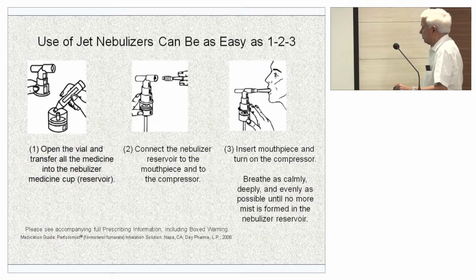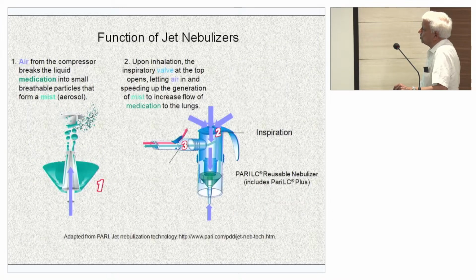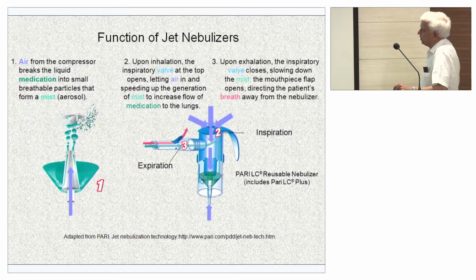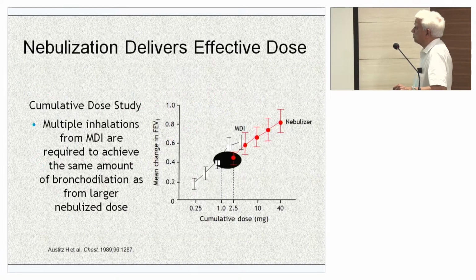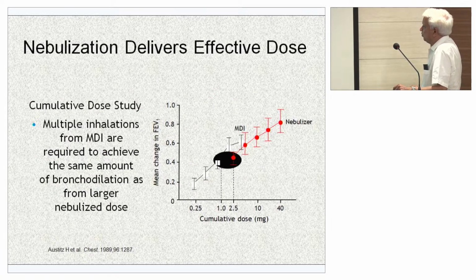The patient just breathes calmly and deeply until no more mist is formed. So basically it is easy to use, you see. As I have said earlier about the jet nebulizer, air or gas is flown through the nozzle, it breaks the liquid drug into finer particles, and when the patient inhales, the expiratory valve closes, and on expiration the expiratory valve opens. So the nebulization delivers the effective dose.